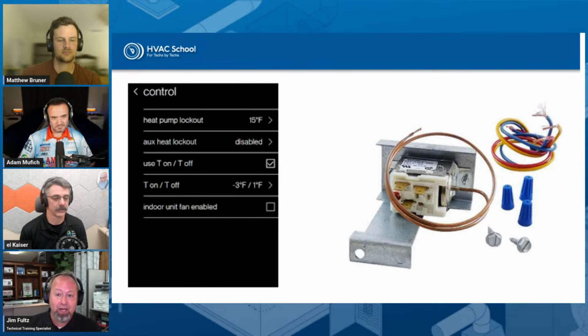Why somebody would want timed, I'm not sure, because you can convert any heat pump over to a demand defrost and save those additional cycles where that heat pump is checking, and have that additional outdoor temperature sensor to be able to run that extra circuit if you've got the wires. If you don't have the wires, then you use something like the Sensi Touch 2, where you can get that temperature directly from the internet.